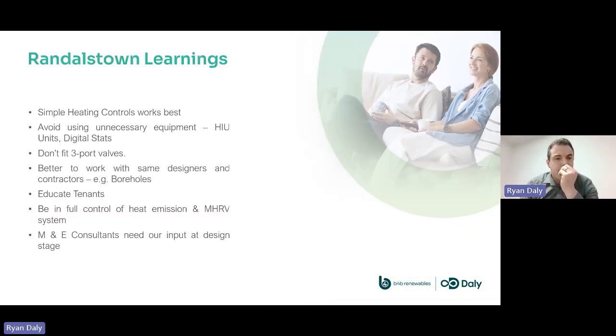So some of the learnings from Randalstown: again, simple heating controls work best. One of the philosophies I would have is don't give people controls that they don't know how to use. We even found over the years that a simple enough time clock can be very difficult for a lot of people to program. So we try and stay away from all that kind of stuff and keep it very simple. Avoid using unnecessary equipment. I mentioned the HIU units. In that scheme, they fitted 3-port valves, which we didn't think were required, but again, it was on the design. That was simply to divert the heated water from the underfloor manifold back to the plant room.